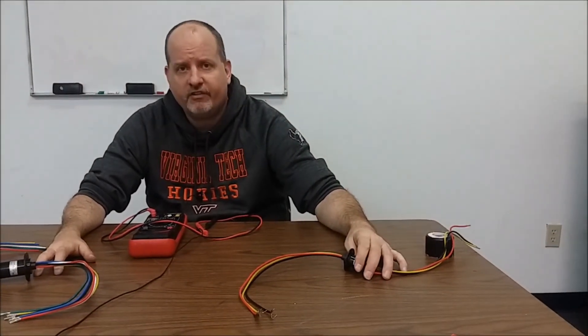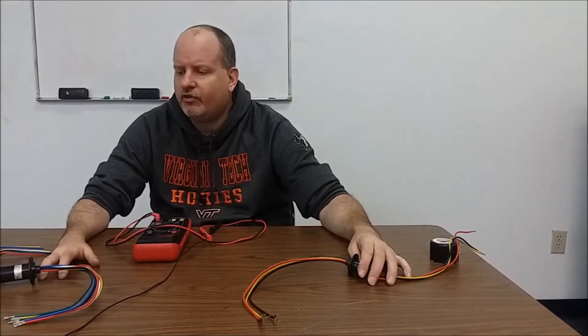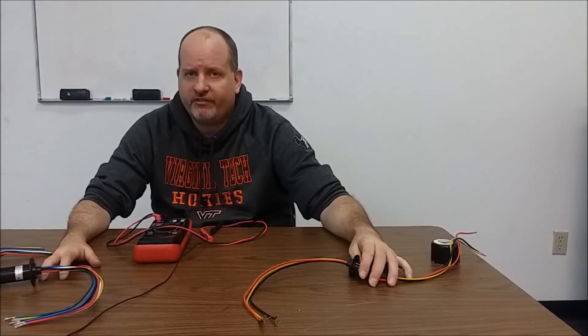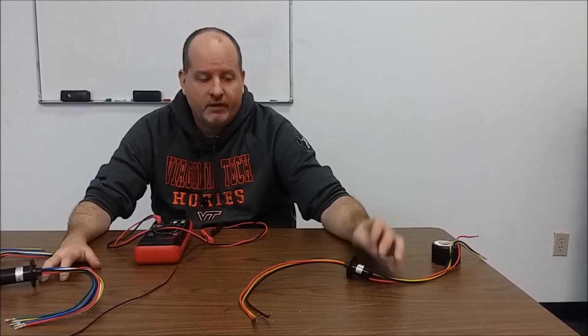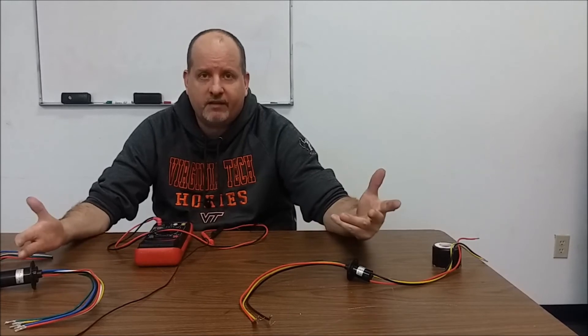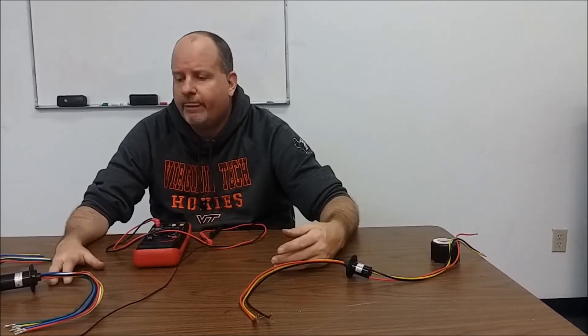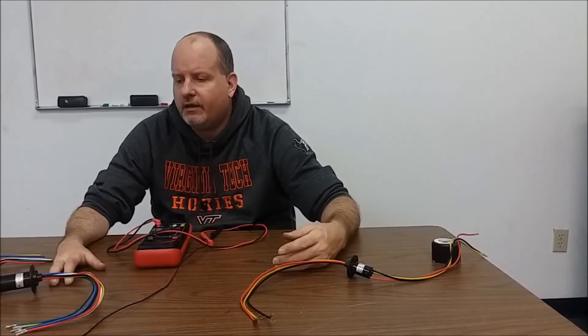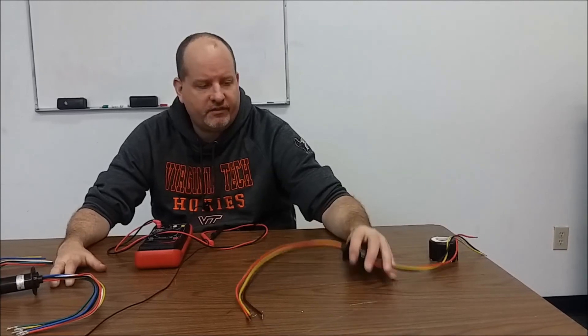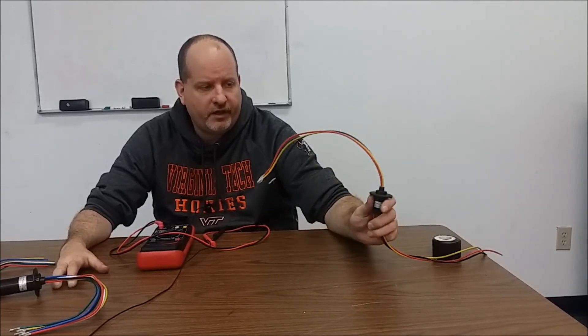The second thing is, a common misconception with wind turbines is that if you have a three-phase wind turbine and I have 60 amps, that means that exactly 20 amps goes through each conductor. That's not the case. There is a higher current flow on each wire. That is why with our 12 and 24 volt wind turbines that actually make power - we make lots of power here at Hurricane - you cannot have the success. This came out of a 48 volt wind turbine.